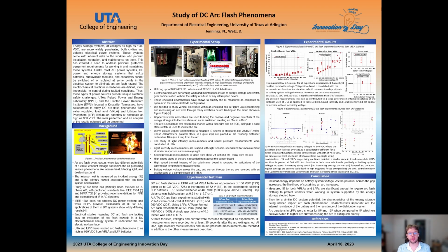And finally, just some closing words. So this showed that incident energy likely depends on battery voltage, as this is primarily driven by the improved conduction across the gap with increasing voltage, driving higher currents. Also, we show that for VRLAs and LFPs, the incident energy is significant enough to recommend and require arc flash PPE to protect workers from any incident or hazard present.